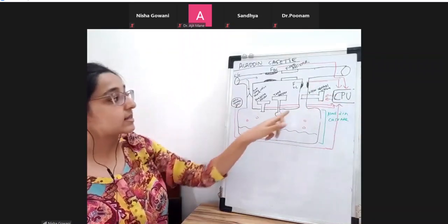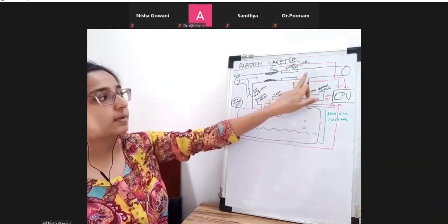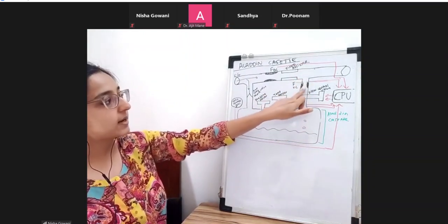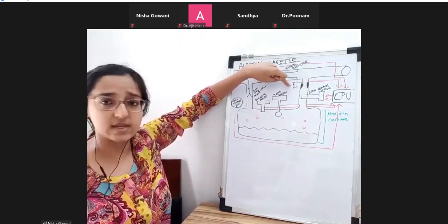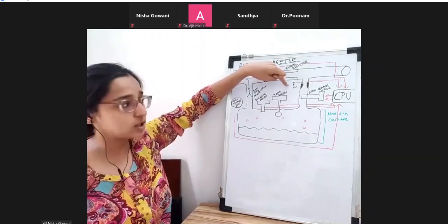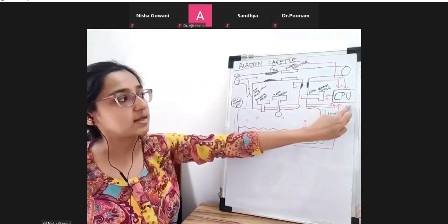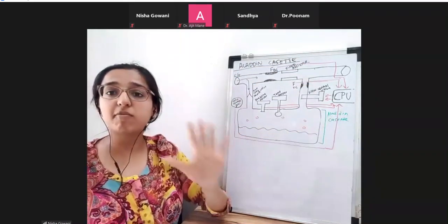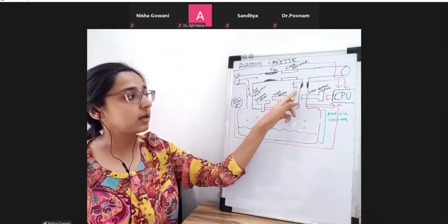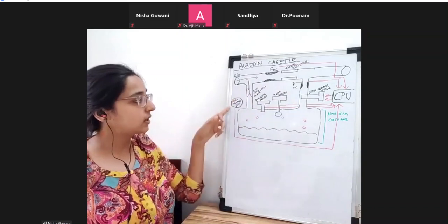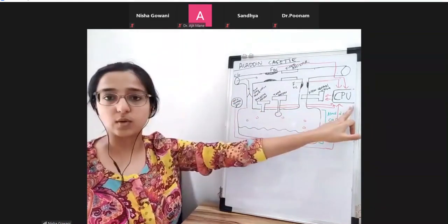Next, there is this. This is the vaporizing chamber output, the outlet of the vaporizing chamber. Along the outlet you have another flow measurement sensor, located in the vaporizing chamber outlet, and this flow also is sensed by the CPU. So the CPU is getting inputs from 5 places: the bypass chamber flow measurement, the vaporizing chamber flow measurement, the concentration control dial, the pressure sensor, and the temperature sensor. All of these inputs go to the CPU.